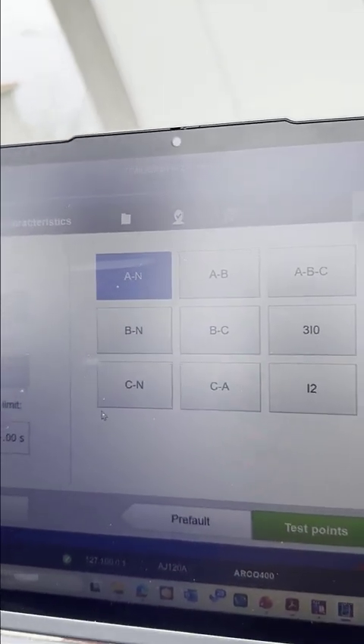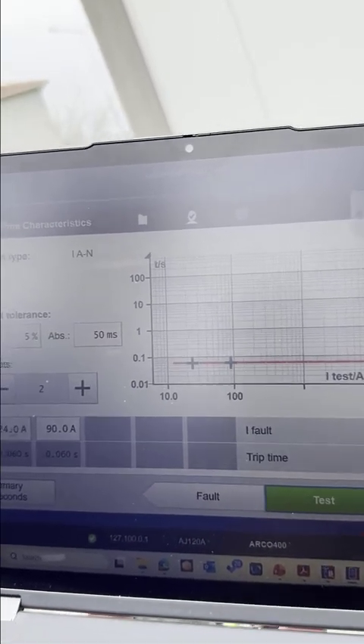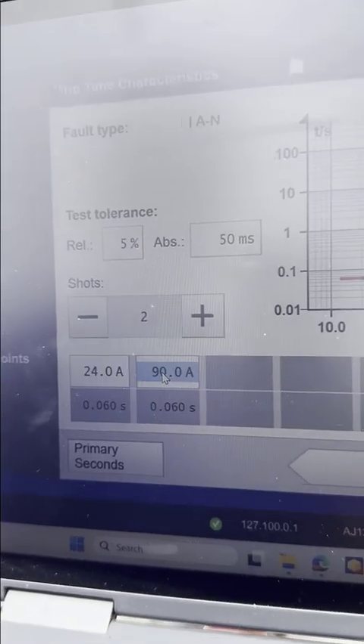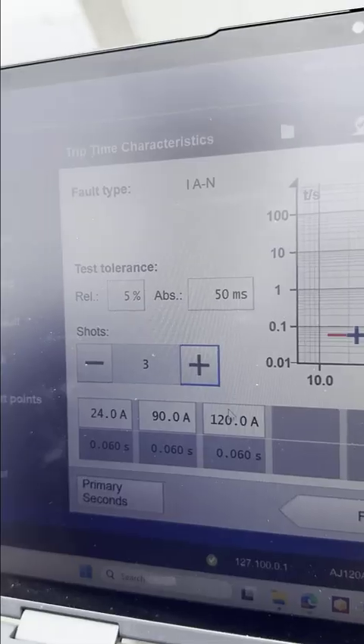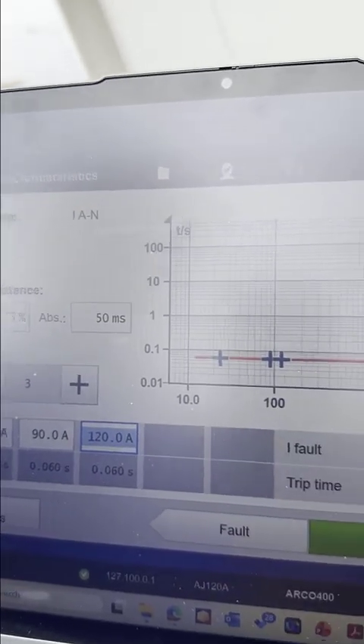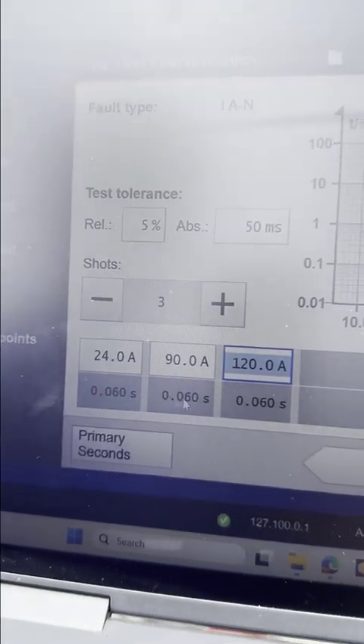Then we can go for the fault. We can select the A to N since we are going to test the earth fault protection. Then you can define the test shots now as 24 or 90 amp. You can put it like third one also like 120 amp, but all of them will be tripped with a 60 millisecond because it's a definite time.